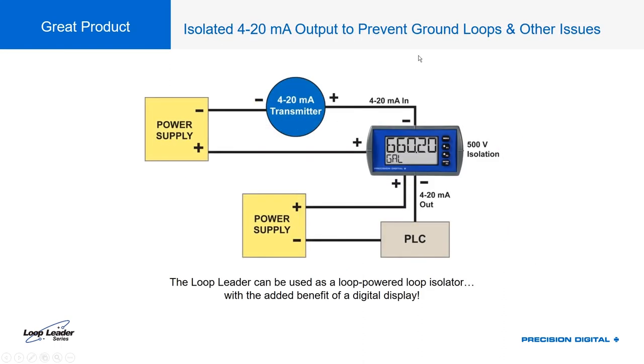The Loop Leader's 4-20 milliamp output lets you isolate two separate 4-20 milliamp loops. In a control cabinet scenario with a field power supply and transmitter on one side and a PLC loop power supply on the other, the Loop Leader provides electrical isolation between those two lines, making the system more noise resistant and preventing ground loops when wiring multiple systems into a PLC.